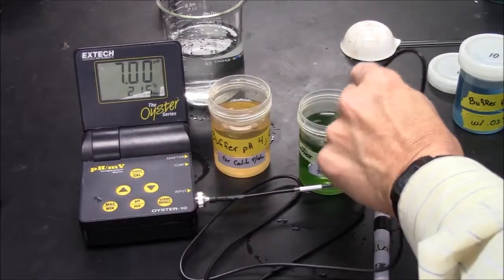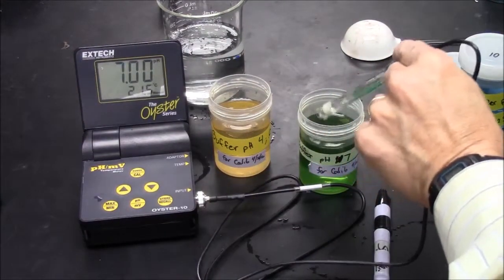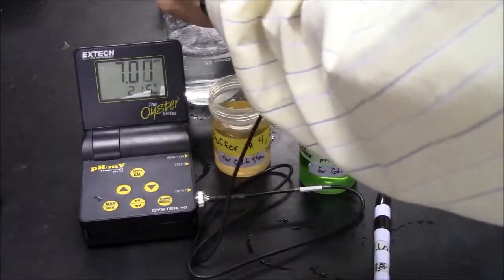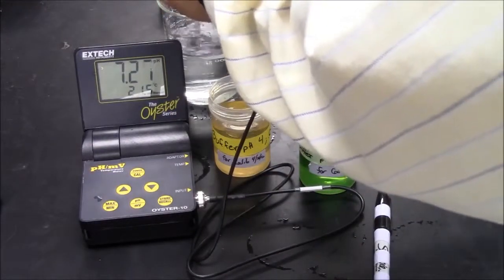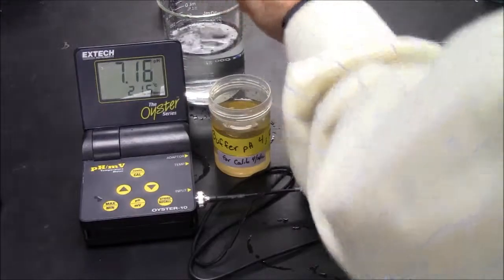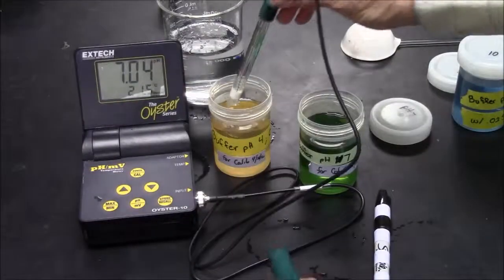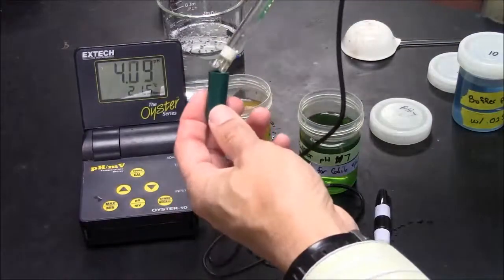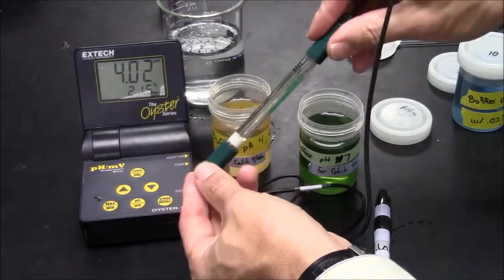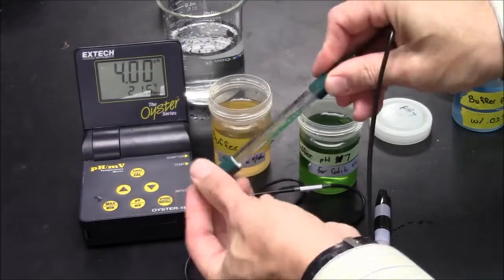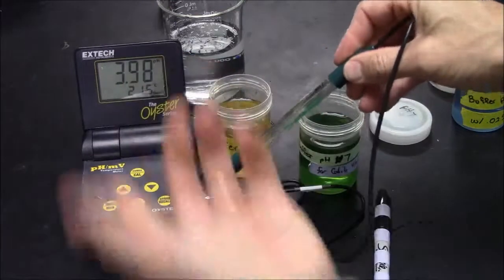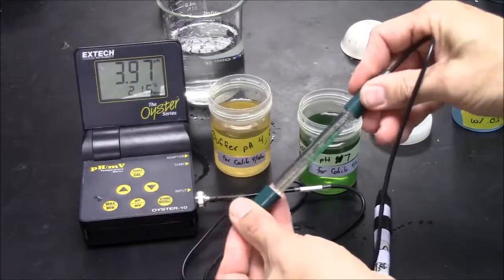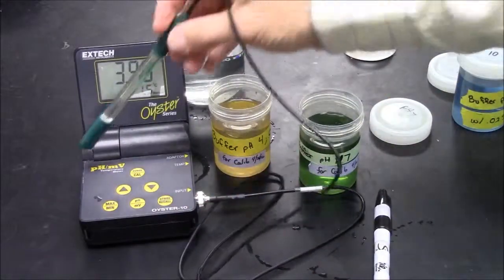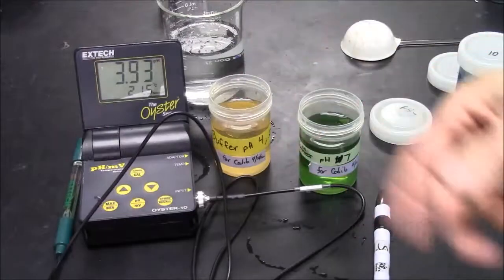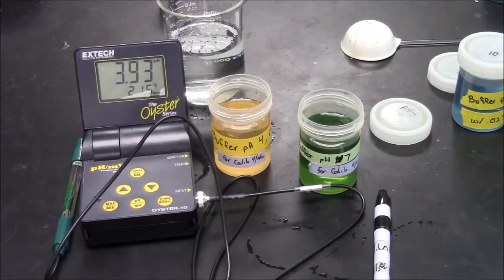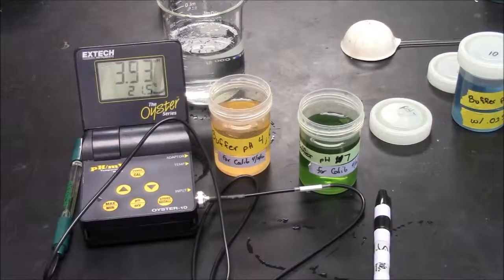If I am putting the electrode away for storage, I rinse off all solutions that are on the electrode. A quick dip into pH 4. This is the buffer or the pH at which it is most happy. Put the cap on. pH reading should be close to 4. And this is ready to be stored overnight or maybe even for a week. Calibration usually lasts about a week.